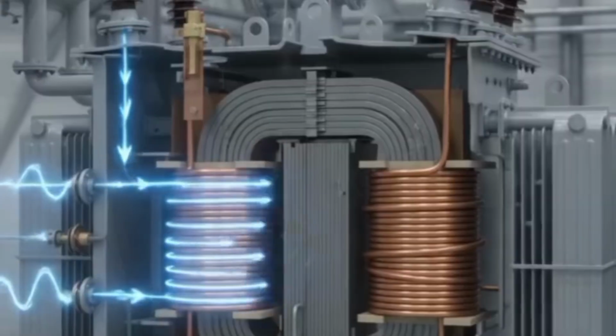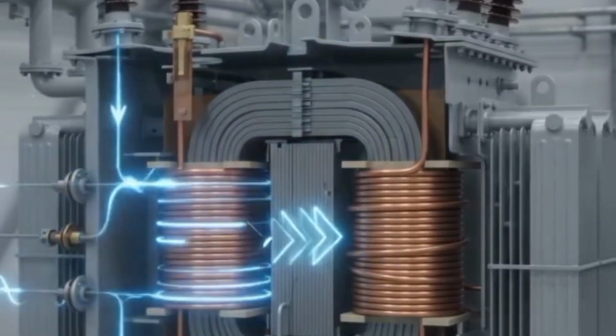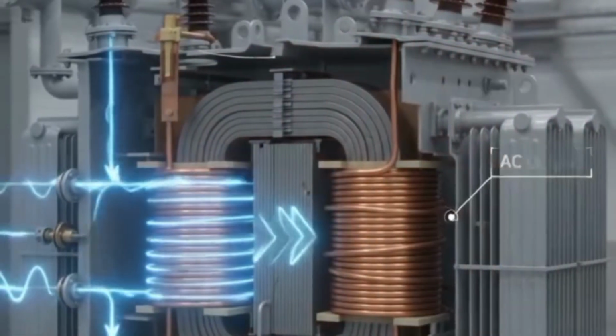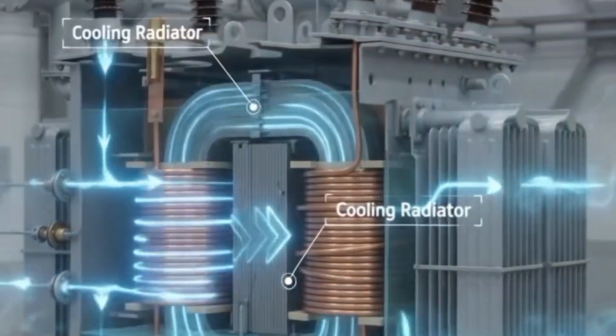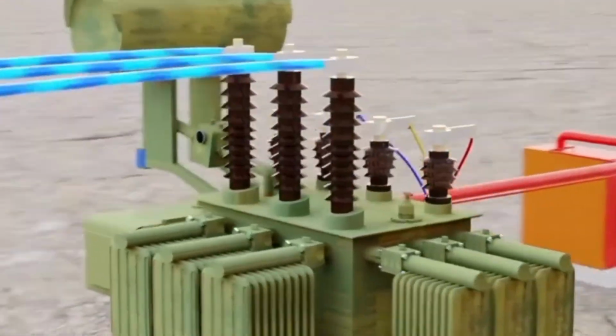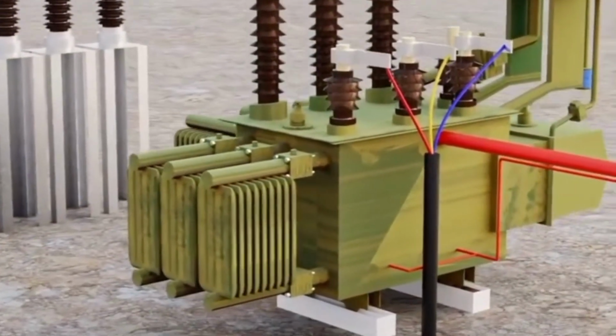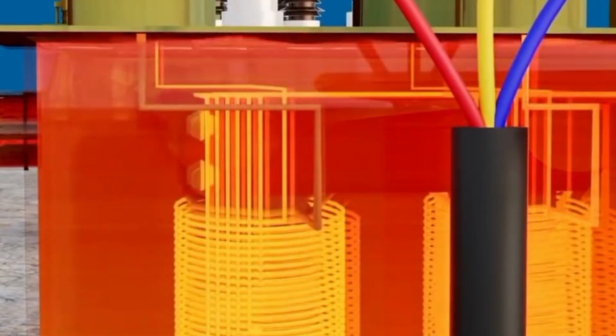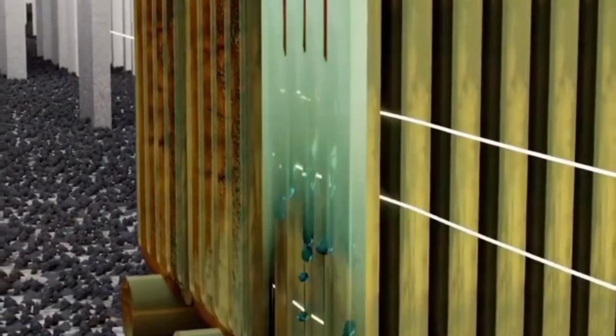At the absolute heart of the transformer is the core. The core is typically constructed from high-grade silicon steel, and it is not a solid block of metal as one might assume. Instead, it is made of hundreds of incredibly thin sheets of steel packed tightly together, known as a laminated iron core. This laminating process is crucial because a solid piece of iron subjected to changing magnetic fields would experience massive energy losses due to swirling internal electrical loops called eddy currents.